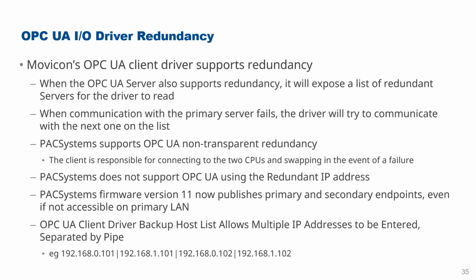So here I've got 2 LANs and 2 devices. Each device is on 2 LANs, and I've got 2 networks there. So I've got 192.168.0 for my primary LAN, 192.168.1 for my secondary LAN, and then my device addresses are 101 for the primary PLC and 102 for the backup PLC. So that's 4 IP addresses, and the way I enter them is as I've entered them here.